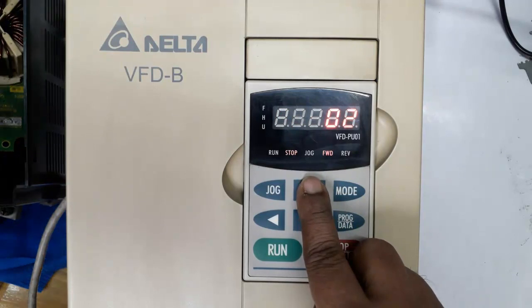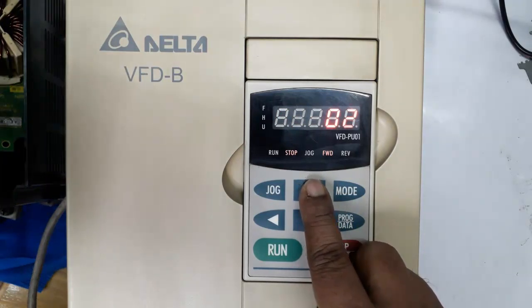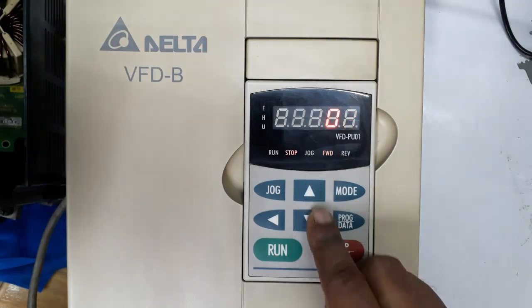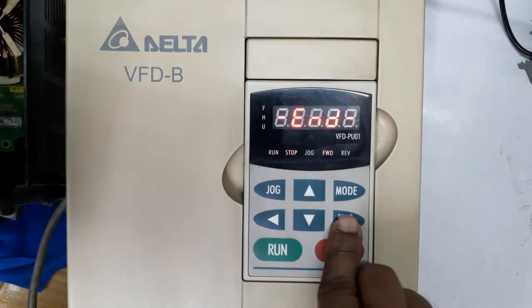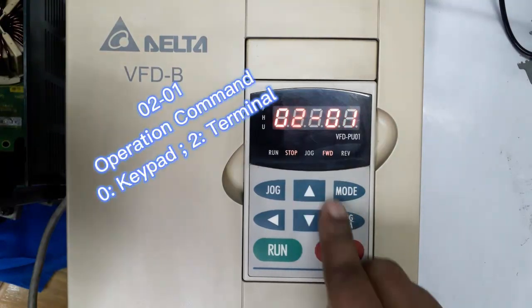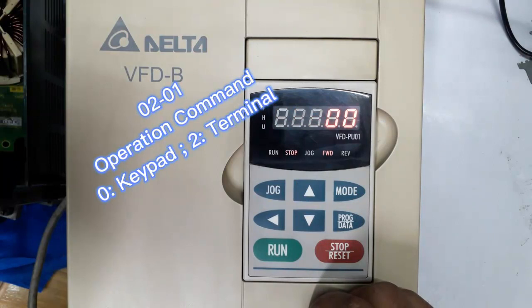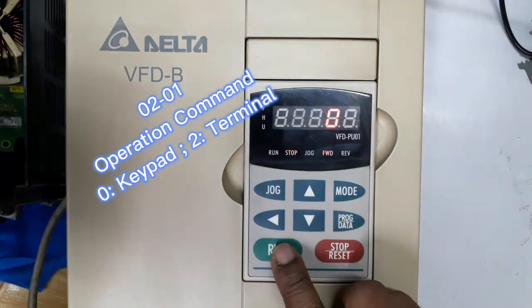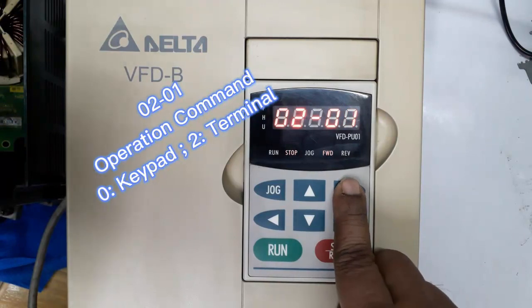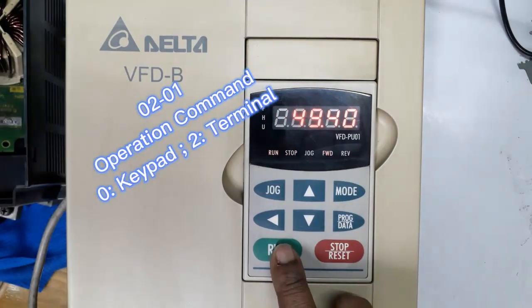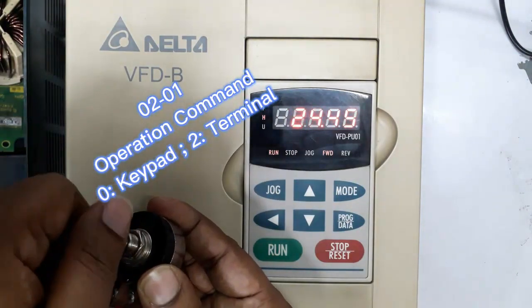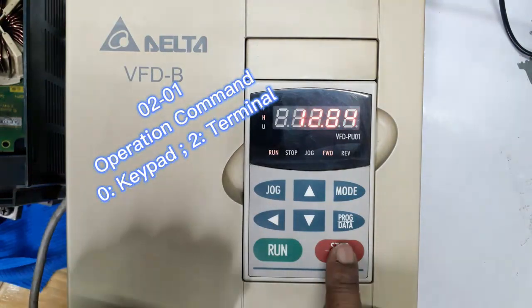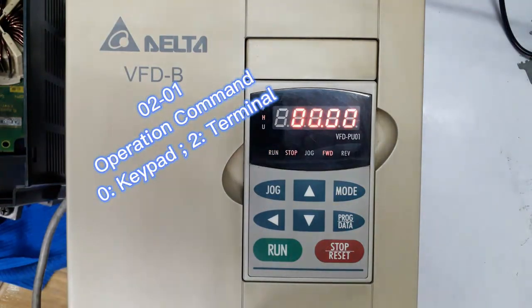Now the drive is in keypad operation and frequency mode by terminal potentiometer. If you set 2, it will be current reference for frequency. So we set here 1 for potentiometer. Now the drive can be run by the run button. We want to set the run command externally. Frequency can be changed by the potentiometer, which we set just a few seconds ago.